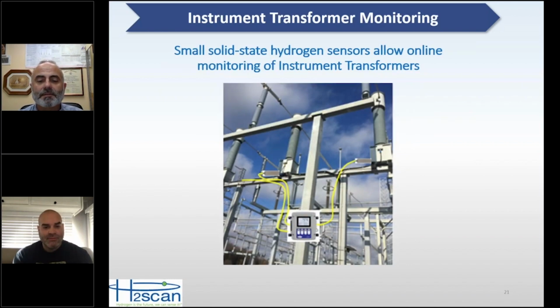Also, there are smaller solid-state hydrogen sensors available today that would allow the monitoring of high-voltage instrument transformers. These typically only have a gallon or 2 of oil, depending on the size. But when they fail, sometimes they do fail violently, and we're working with a customer right now that has some high-voltage instrument transformers, a couple of which have failed recently, and so they're looking at adding real-time hydrogen monitors on their instrument transformers.